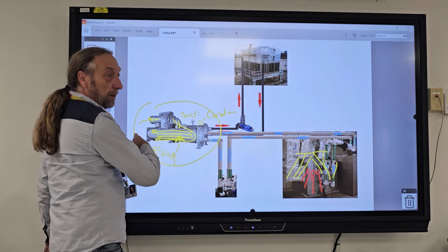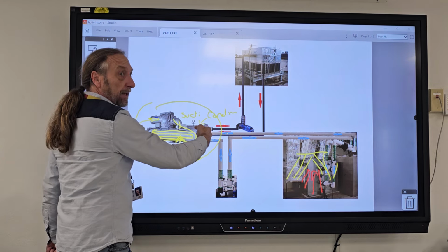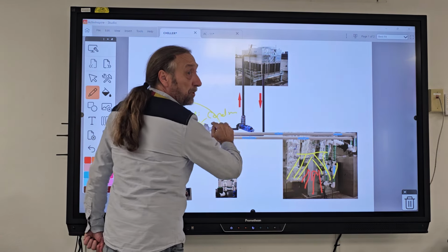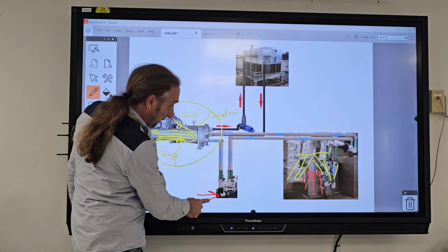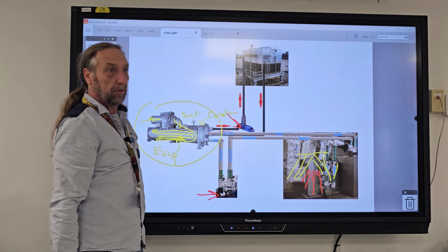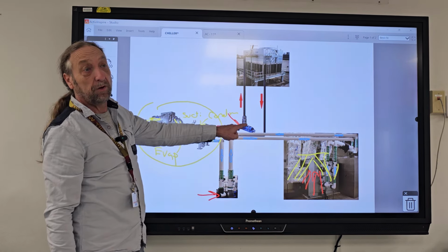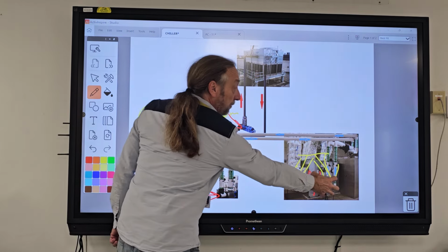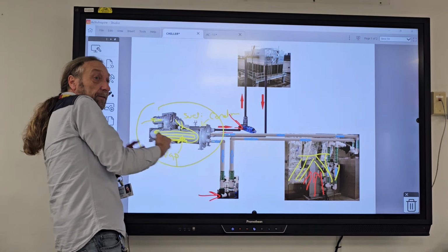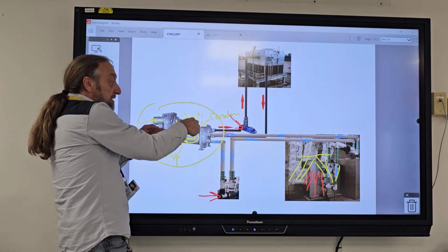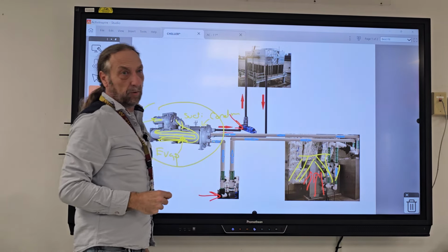But when we bring the heat here, the freon takes the heat to the condenser, and then we have a separate water system. That's why it's two colors. We have a water pump here and a water pump here. One for the chilled water and the other one for the condenser water. So this absorbs the heat in the water. It comes over here. The freon takes the heat, passes the heat to the condenser, and then we pump it up to something called a water tower.